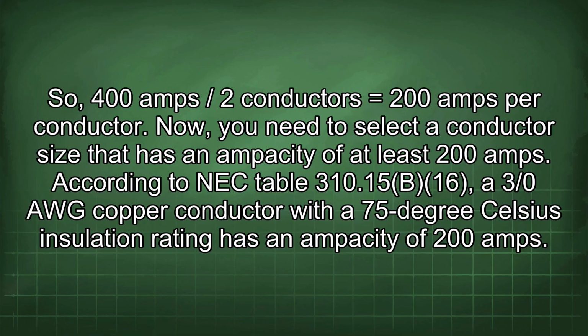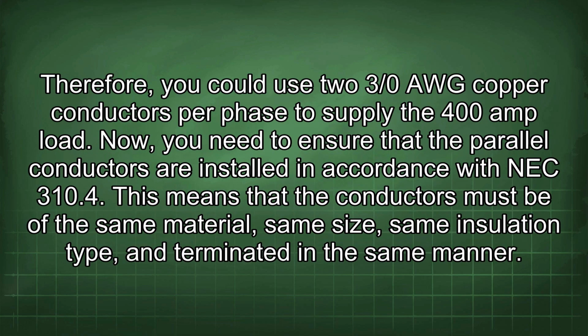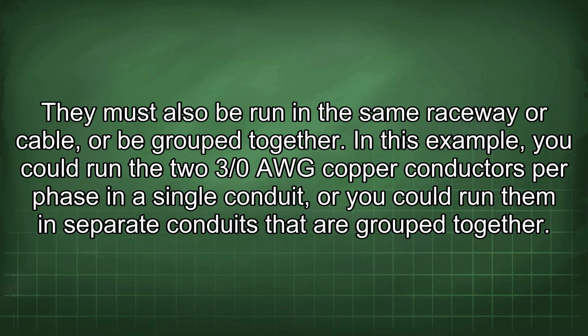According to NEC Table 310.15(B)(16), a 3/0 AWG copper conductor with a 75 degrees Celsius insulation rating has an ampacity of 200 amps. Therefore, you could use 2 3/0 AWG copper conductors per phase to supply the 400 amp load. Now, you need to ensure that the parallel conductors are installed in accordance with NEC 310.4. This means that the conductors must be of the same material, same size, same insulation type, and terminated in the same manner. They must also be run in the same raceway or cable, or be grouped together.